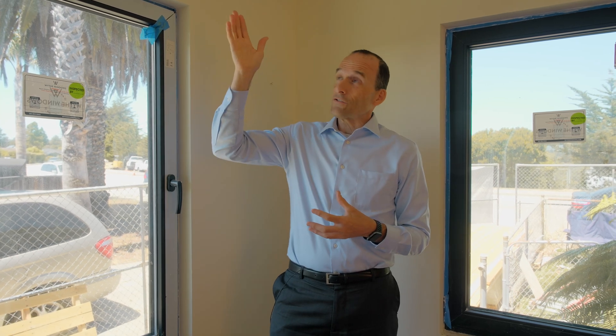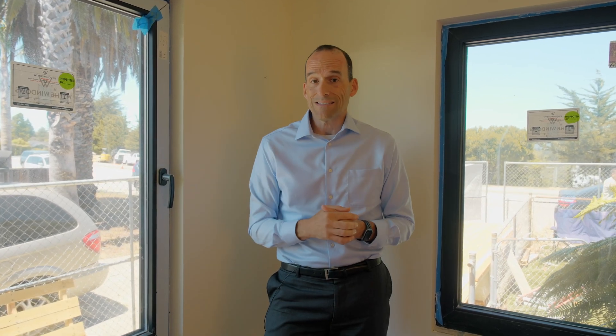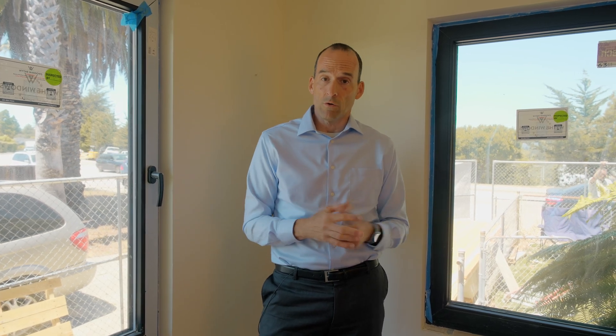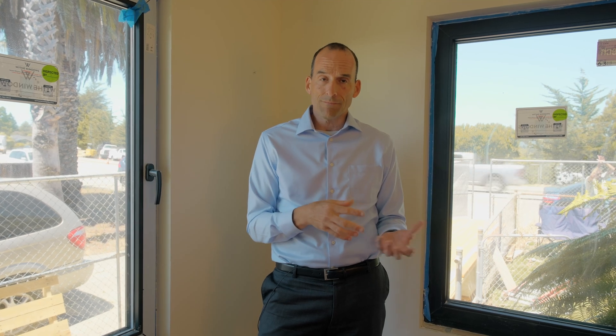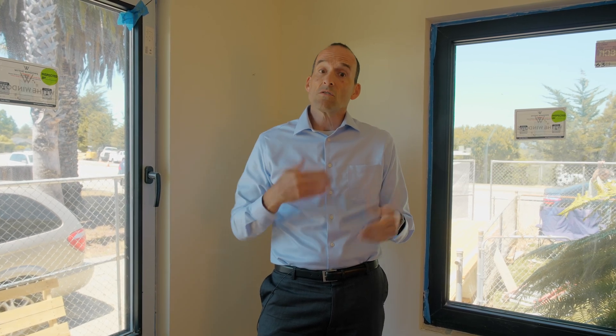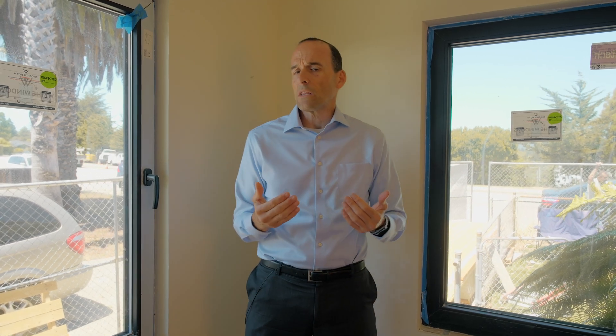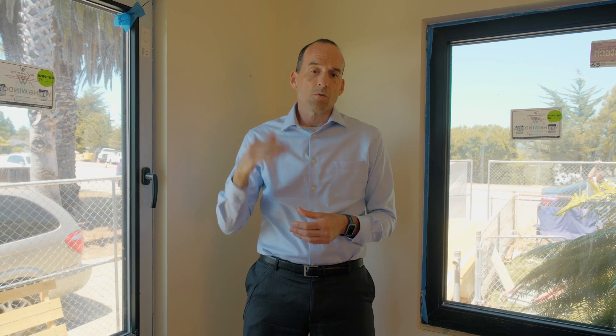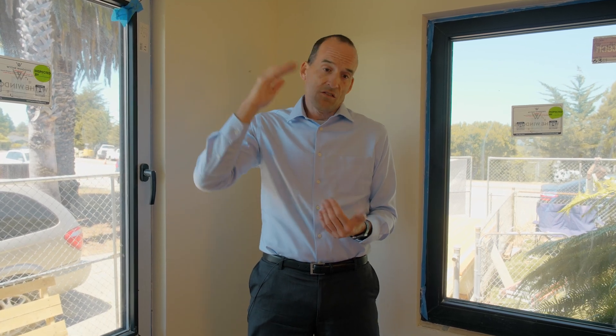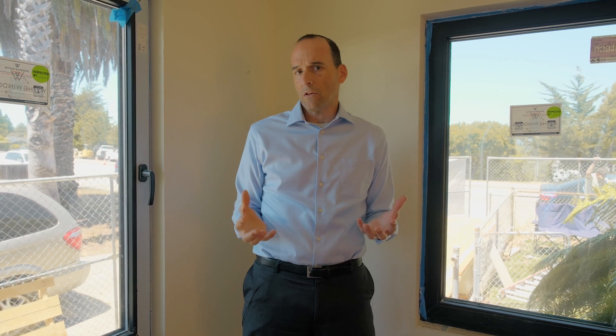This is actually a 12,000 BTU mini split, but we only need 6,000 BTU for this house. We do have other heating and cooling units in this house specifically for individual rooms — it's honestly probably overkill, but the clients wanted more control in the rooms. In the past, this house had a lot of problems with overheating. It didn't have any insulation, which contributed significantly, but it's also facing south with a lot of windows and doors on that side. This system is actually so large that it has trouble getting down to the heat output needed — called turndown capacity — its ability to down-regulate from 100% to 50% or 25% to handle the actual heating and cooling loads in this house.